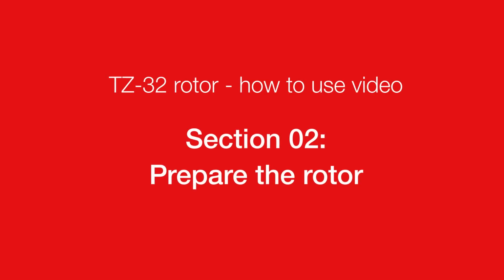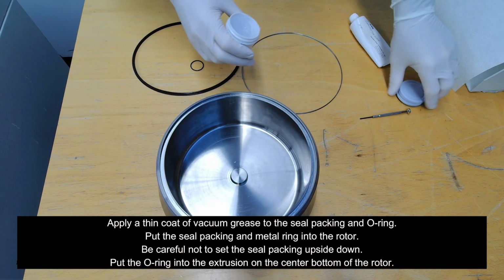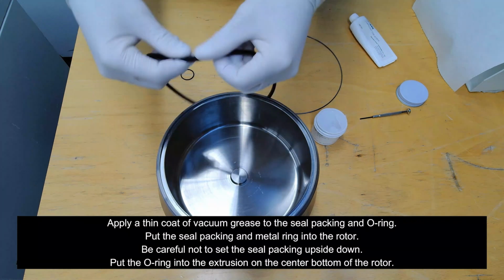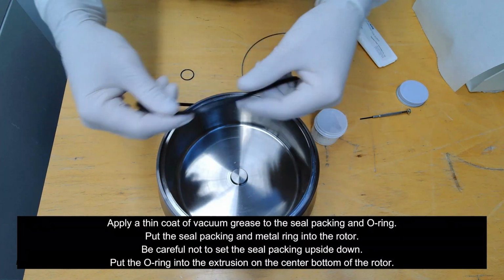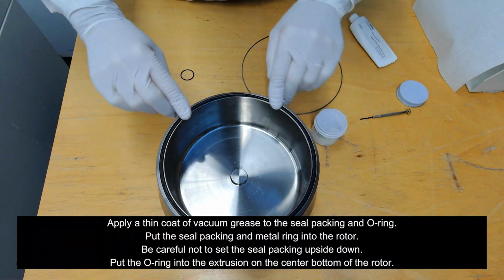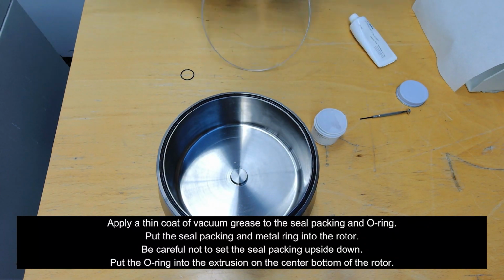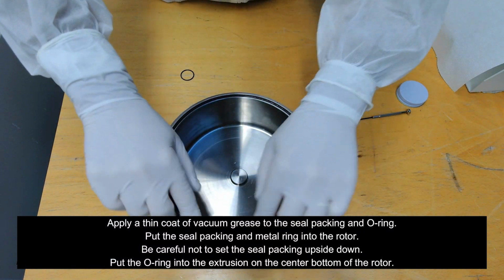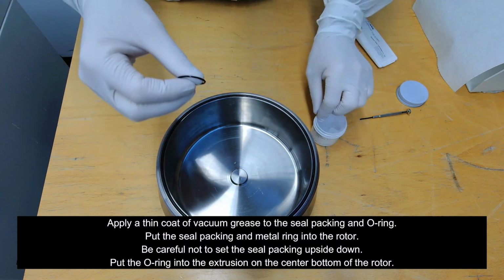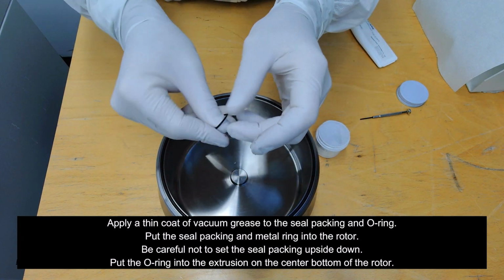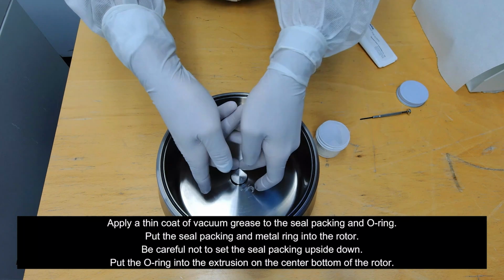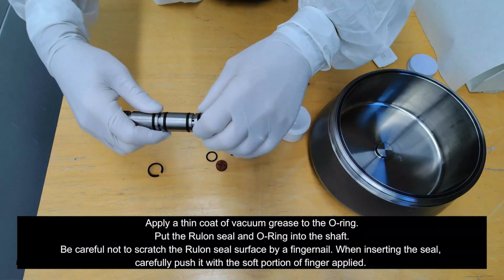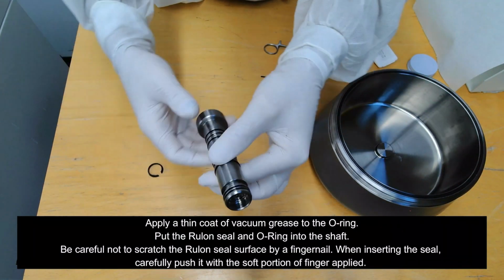How to use video. Section 2. Prepare the rotor. Apply a thin coat of vacuum grease to the seal packing and O-ring. Put the seal packing and metal ring into the rotor. Be careful not to set the seal packing upside down. Put the O-ring into the extrusion of the center bottom of the rotor. Apply a thin coat of vacuum grease to the O-ring.